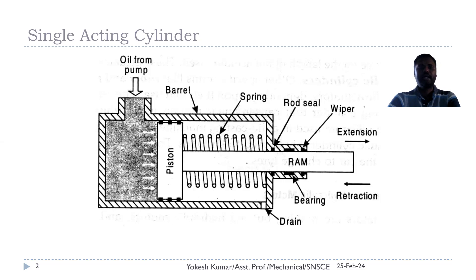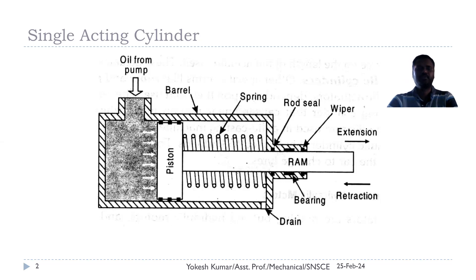Coming to the working: oil is pumped from the pump and enters the blank end of the cylinder. The pump keeps on pumping oil, which increases the pressure of the oil. The increasing oil pressure overcomes the spring pressure and pushes the piston, compressing the spring, which causes extension of the cylinder. Then if we change the direction control valve, the oil from the blank end of the cylinder is returned back into the reservoir.